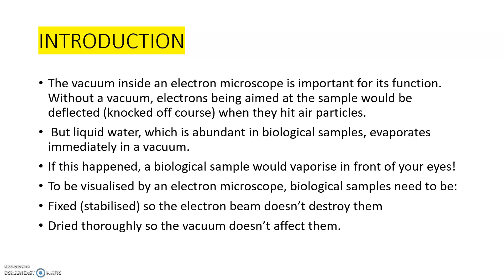The vacuum inside the electron microscope is also important for its function. Without a vacuum, electrons aimed at the sample would be deflected when they hit air particles. Additionally, liquid water, which is abundant in biological samples, evaporates immediately in the vacuum. If this happens, the biological sample would vaporize. Therefore, samples must first be fixed so the electron beam does not destroy them, and also thoroughly dried so the vacuum does not affect them.